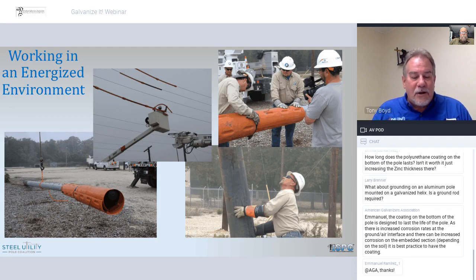You always have to make sure that your choker is secure. One of the problems of steel poles is if you use some types of choker, as you go to lift it, the choker will actually slip up the pole. So make sure that the pole choker is not going to slip as you lift it up. Jim's taking his mouse and kind of moving it around the protective cover that the guys are putting on the top. We've always done that with wooden poles. Any crew that I've worked with, doing any safety work, we've always covered the poles up, sticking them up in the energized line. You see the one picture there of the guy putting line hose on.